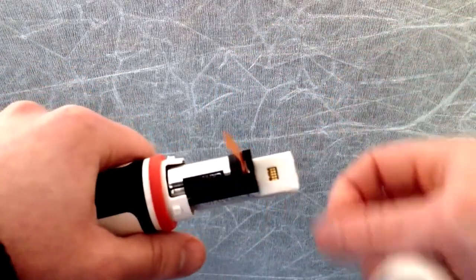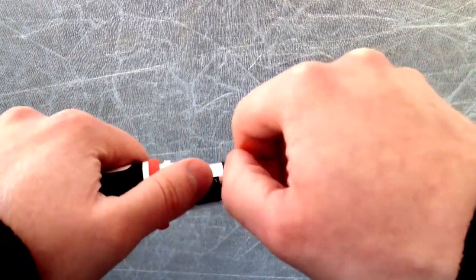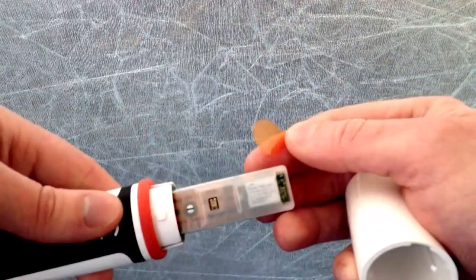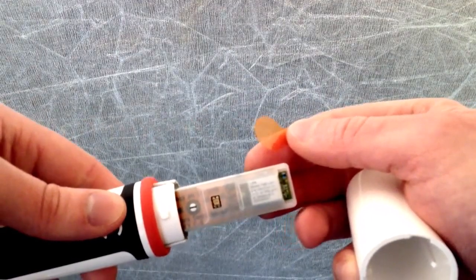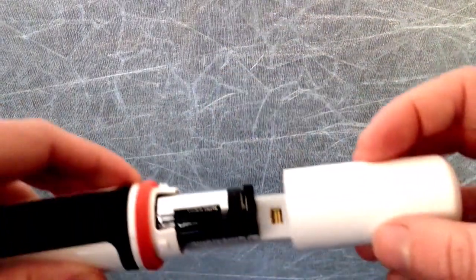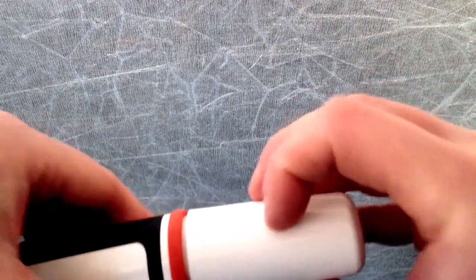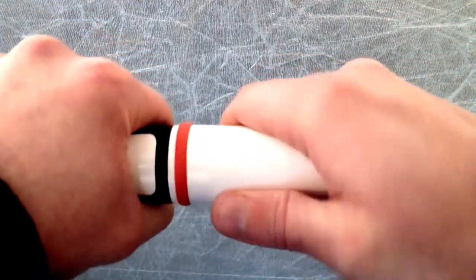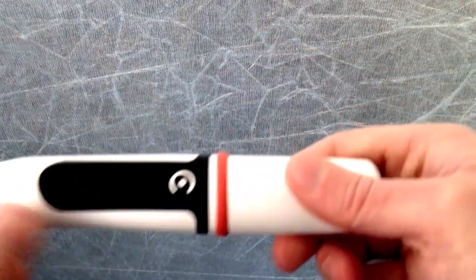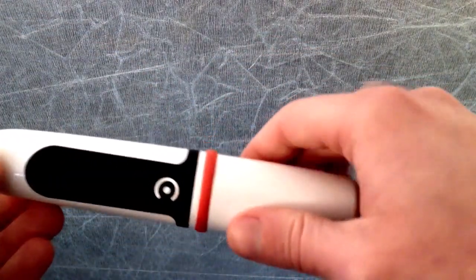Inside you will find there is a battery isolation tab. Remove this, and on the underside a red LED will blink to let you know that the probe now has power. You can throw the tab away. Replace the end cap by pressing on and turning clockwise. Now set the probe aside so it can initialize and grab your memo.